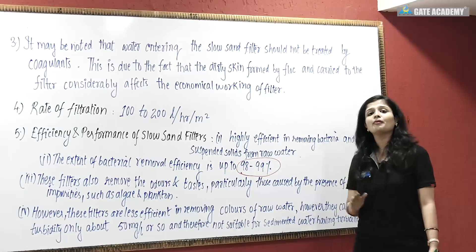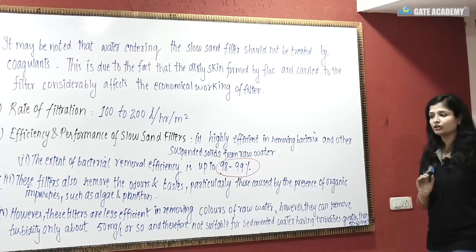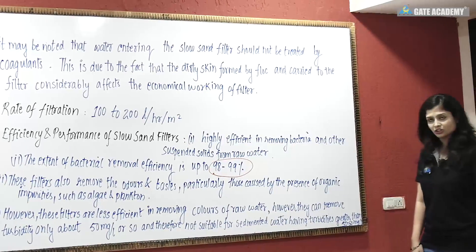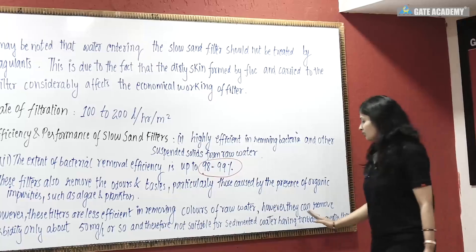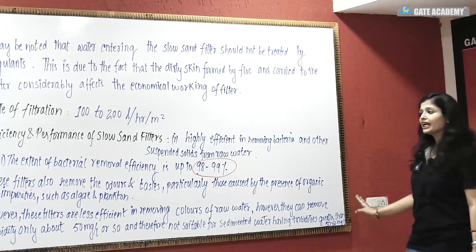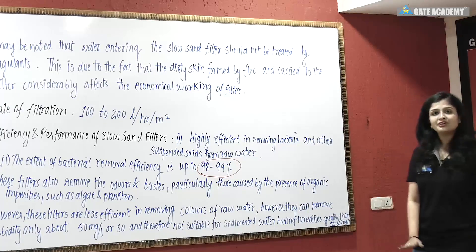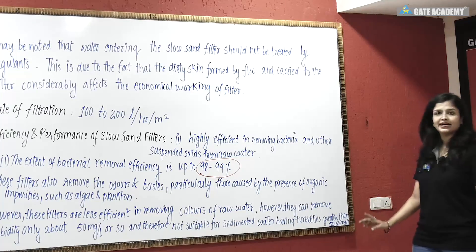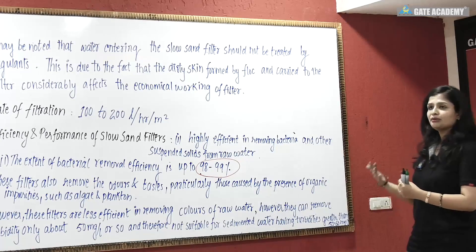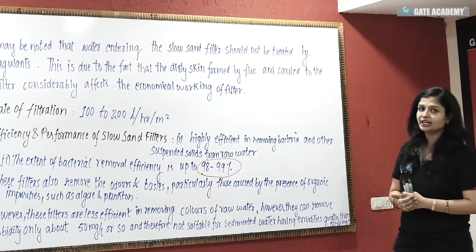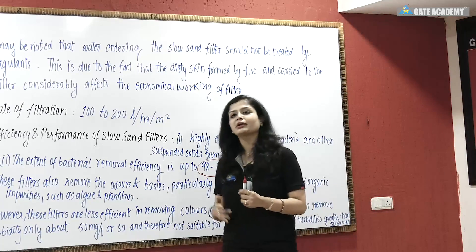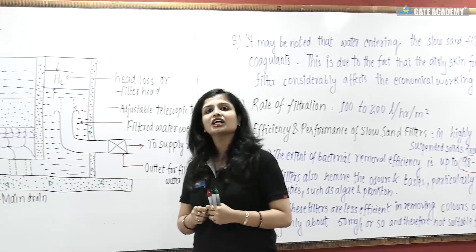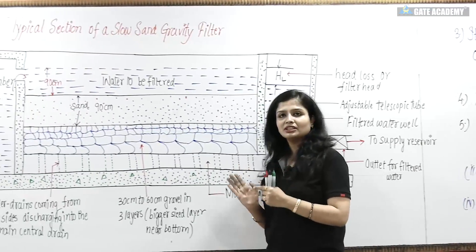These filters can remove turbidity only up to 50 mg per liter, and therefore are not suitable for water having turbidities greater than 50 to 60 mg per liter. If the turbidity is more than 50 mg per liter, you cannot use slow sand gravity filters. Similarly, if you don't have enough area for setup, or if you need to supply water for a large population requiring high volumes, slow sand gravity filters are not suitable.